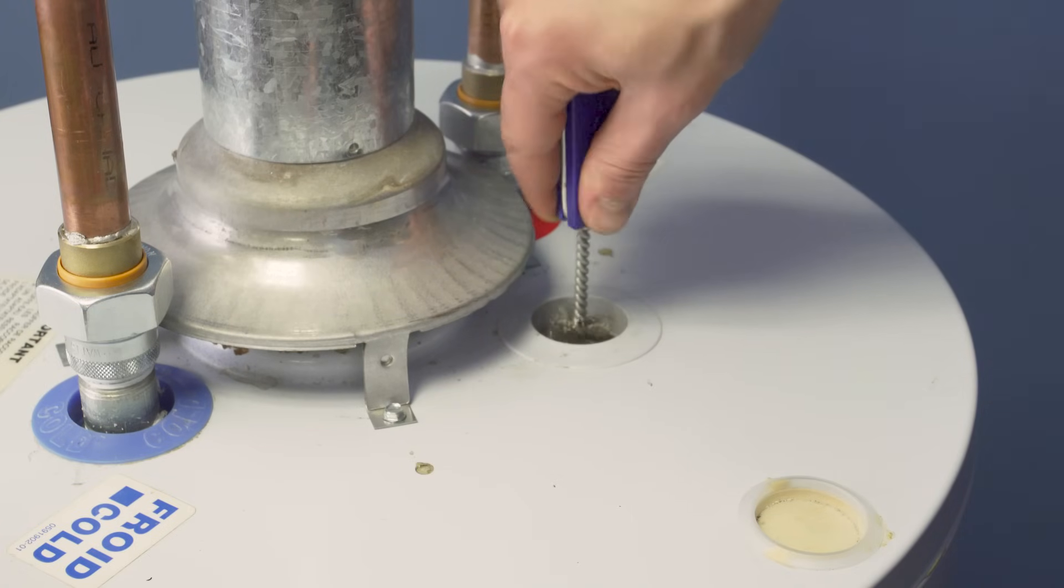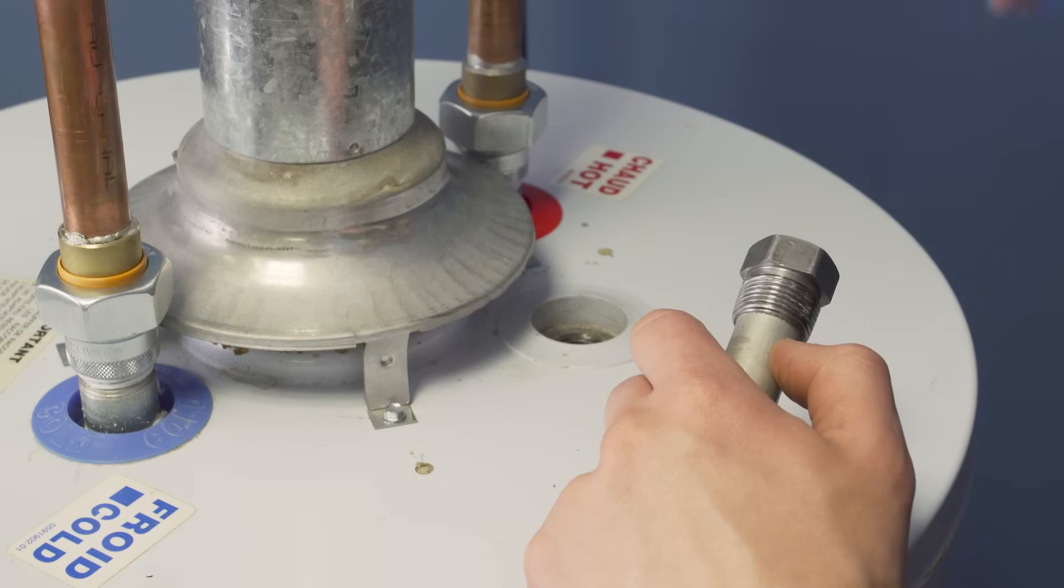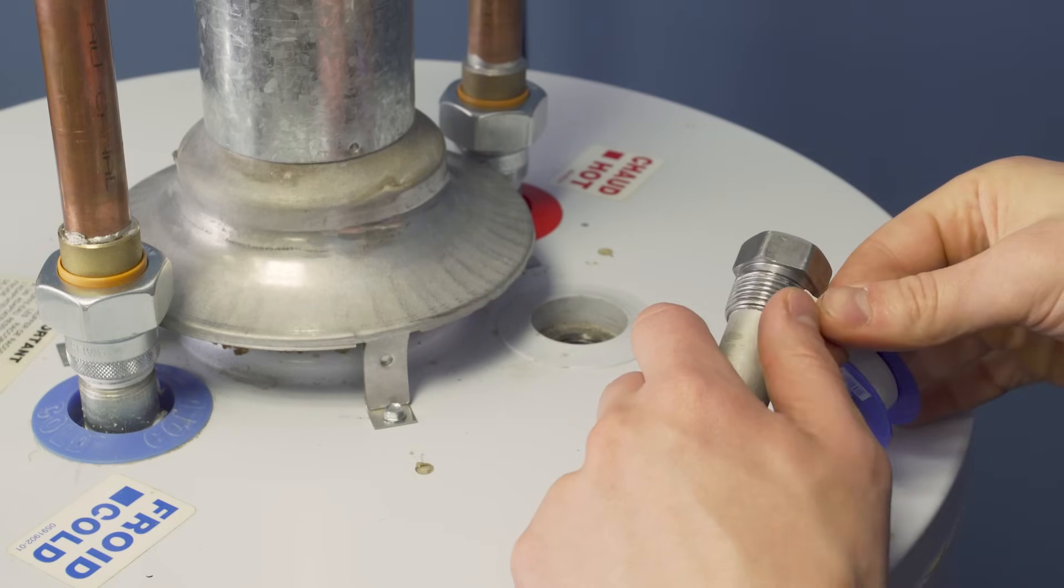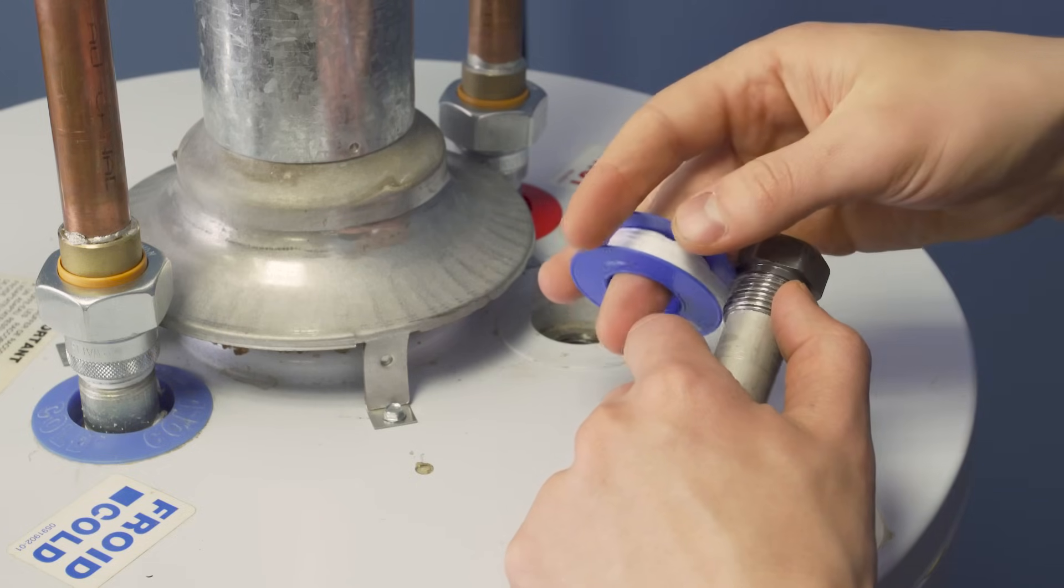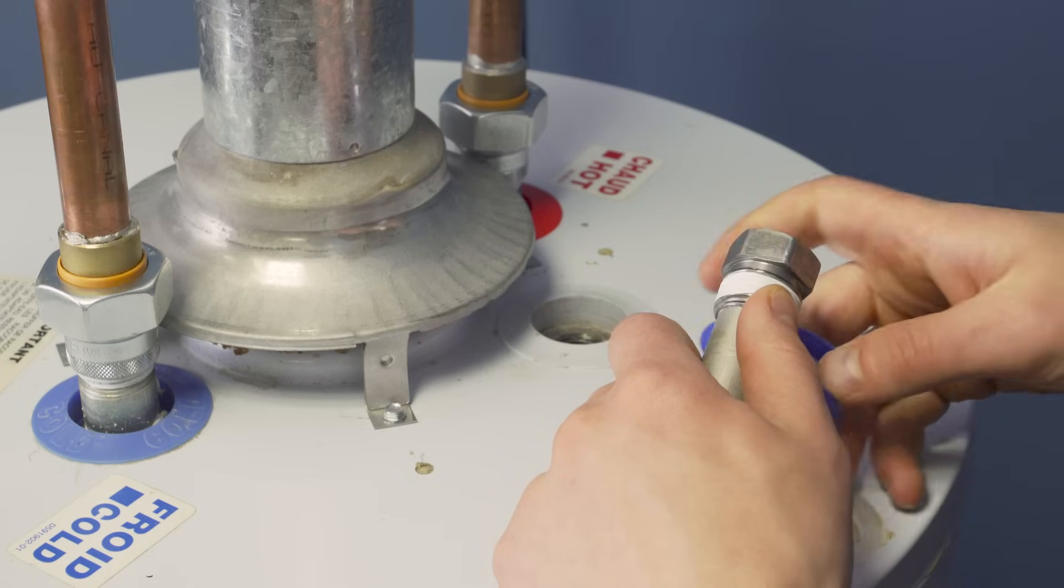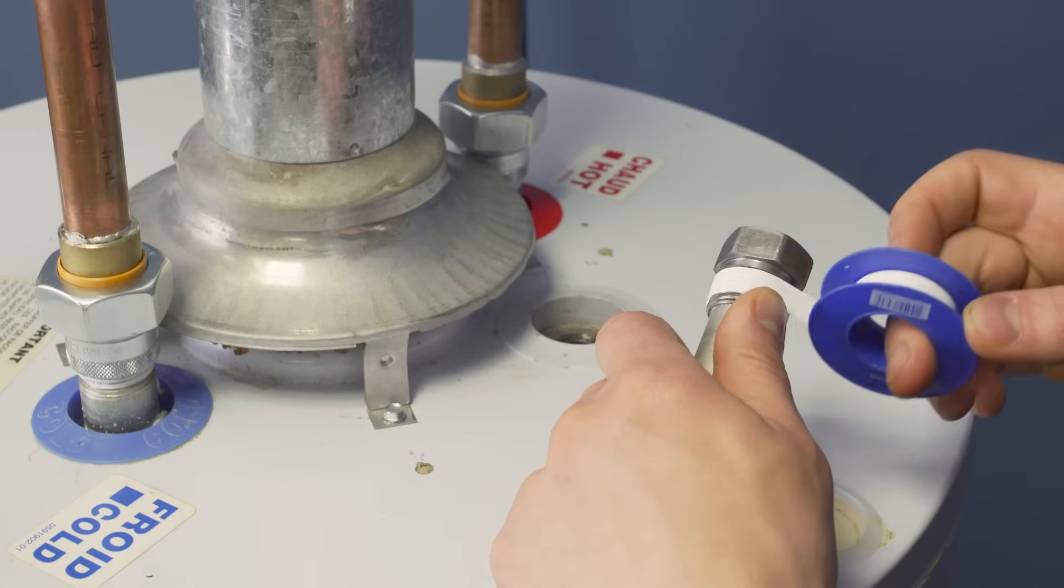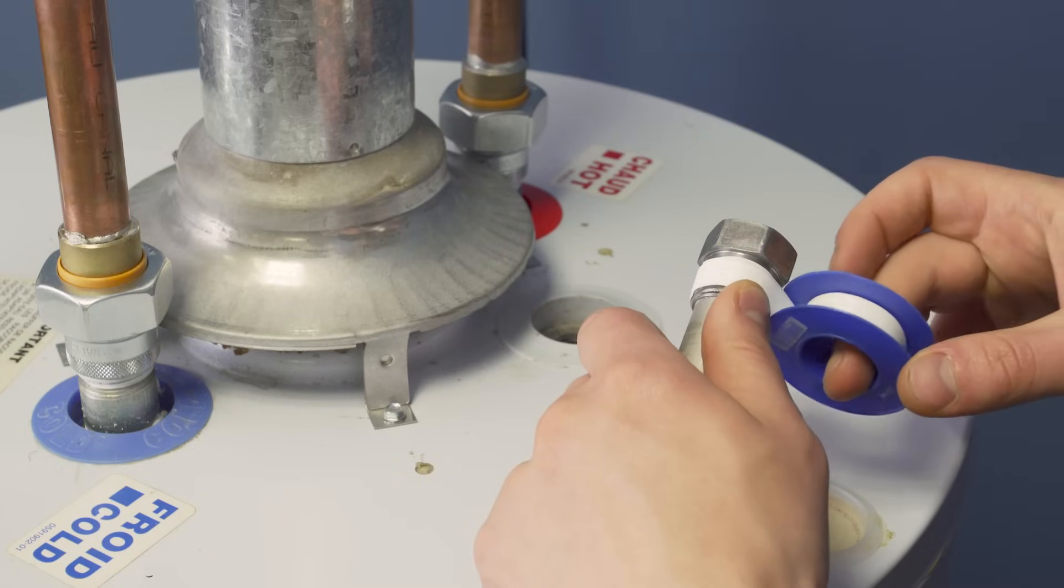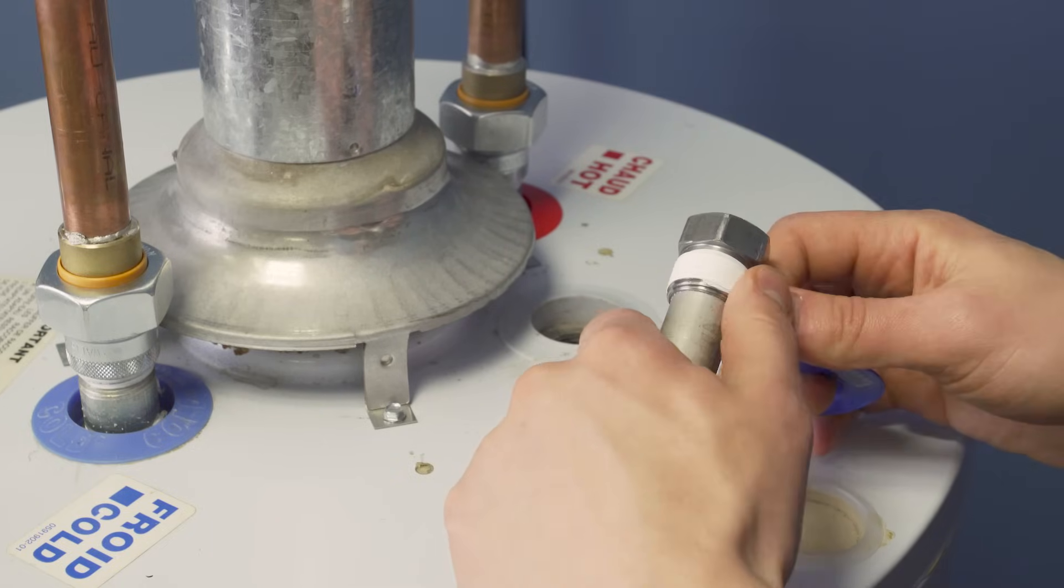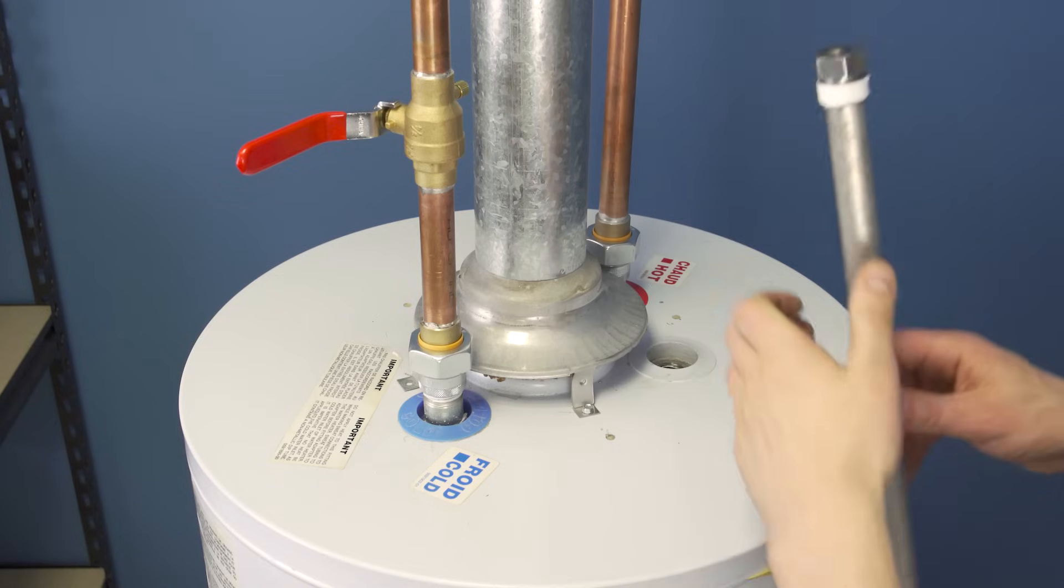To get a good seal, it's best to clean up the threads with a wire brush. Next apply the teflon tape. This will help seal the threads and make it easier to remove and check the rod. Looking at the threads, tape is always applied in a clockwise direction, so that the tape stays on when tightened. Wrap 3 to 6 times, keeping it tight the whole way through. Leave the last part of the thread bare to prevent any tape from breaking off into the tank.